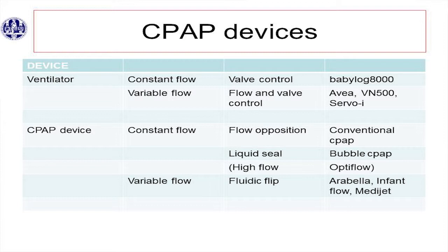Theoretically. Variable flow responds to the demand, so the valves are servo controlled, and that's what our Avea does. In the VN500, is that the Babylog or not? The VN500, and the Servo-i. These are examples. Then the CPAP devices, can you divide between constant flow and variable flow? Constant flow is the conventional way. I don't think anyone else uses it, this has been abandoned. Most of you use bubble CPAP, or the fluidic flip. That's the InfantFlow Driver, Medijet, Arabella. They have different mechanisms, the liquid seal and the fluidic flip. We'll come back to that. So these are the options you have.